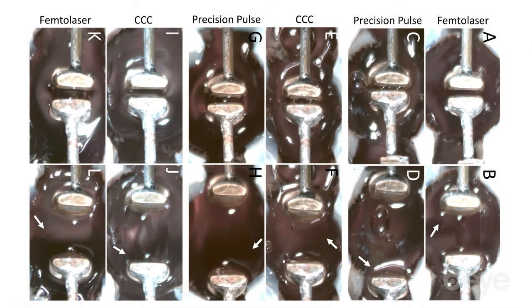One of the real unexpected findings was that the Zepto capsulotomy appears to be extremely strong. The company devised a force gauge machine to consistently test capsulotomies in cadaver eyes, comparing them to the femto capsulotomy as well as the manual capsulotomy using paired human cadaver eyes. These results, published this February, convincingly showed that in each case the Zepto was stronger than manual and stronger than the femto capsulotomy in terms of resistance to tearing, which is very important.